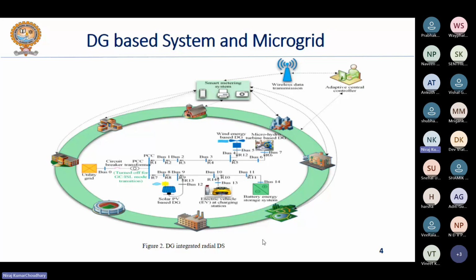Now, what is the basic difference that we need to understand? If the mode of operation changes from grid connected mode to islanded mode, then basically this is a topological change. With every topological change, there will be a change in the fault current capacity or fault current contribution in the network. Now you know that protective devices mainly work on the basis of current magnitude. If you talk about the low voltage or medium voltage network, then mainly overcurrent protection schemes are used, especially at the medium voltage and low voltage network, in the form of overcurrent relays. So if the current contribution changes, then the settings of the protective device need to be changed. So your protection scheme should be adaptive to all the topological changes that may occur in any microgrid system.